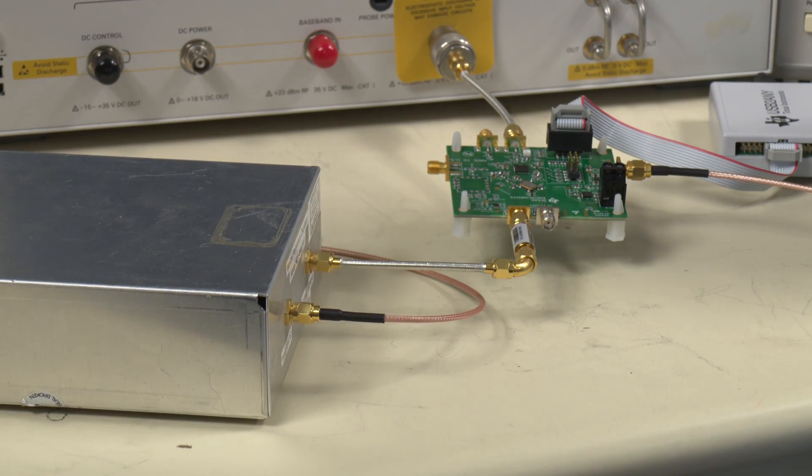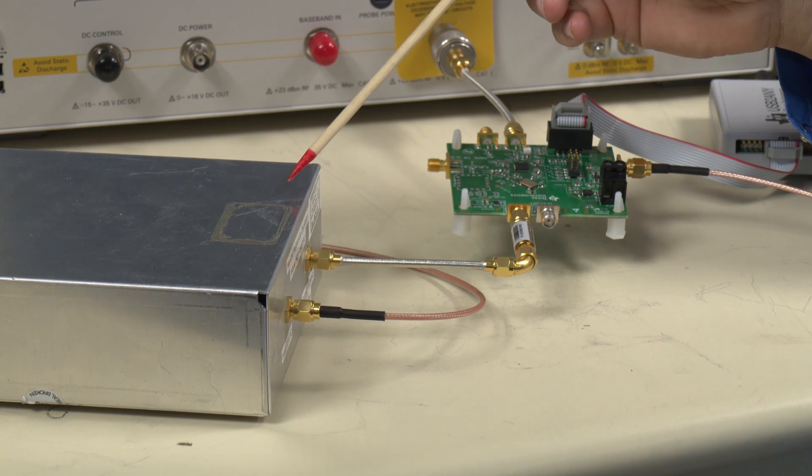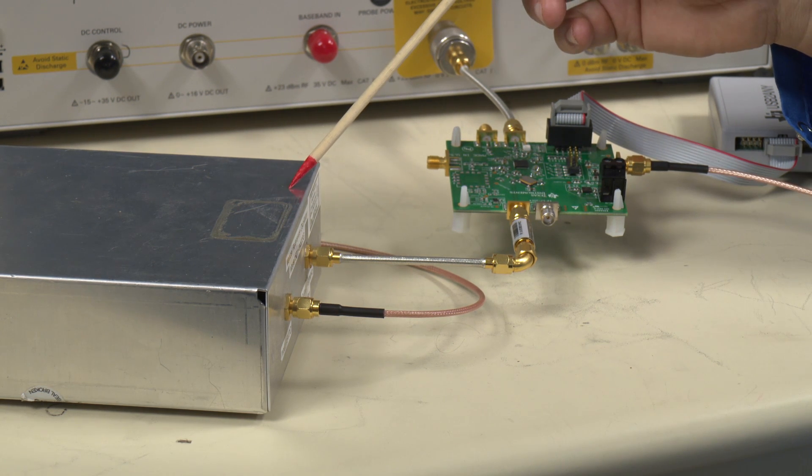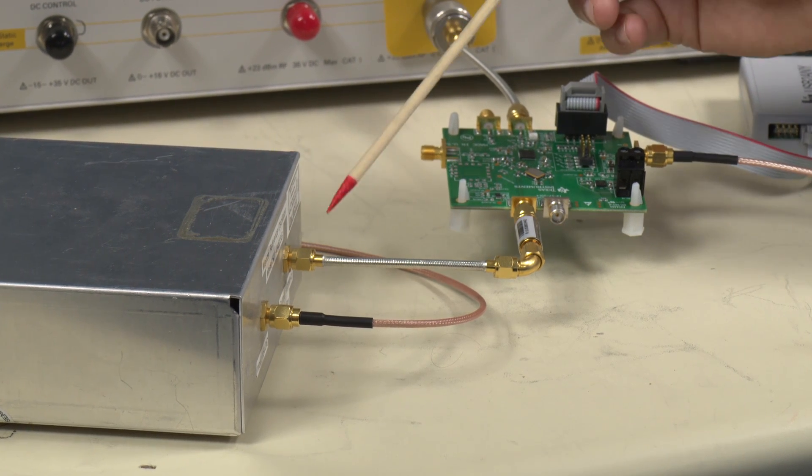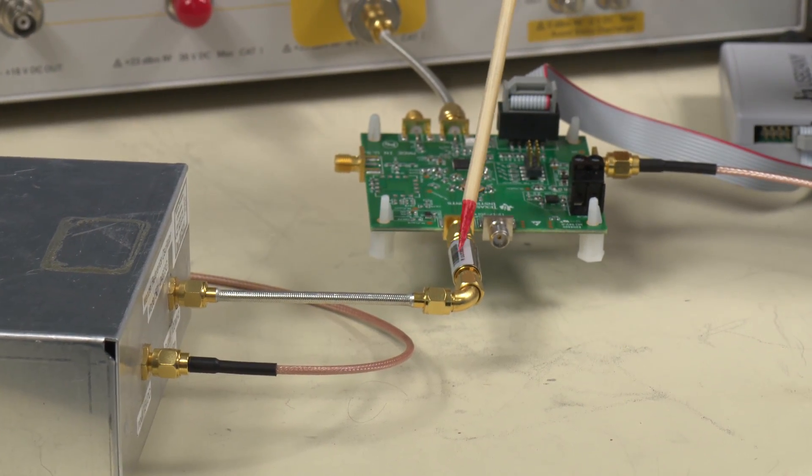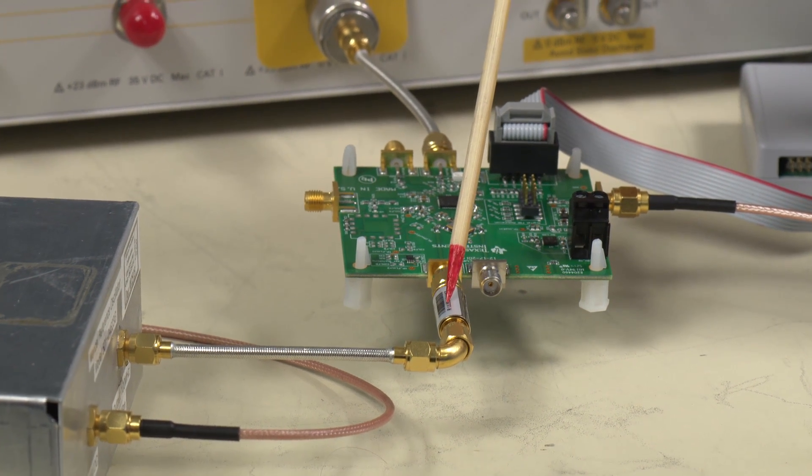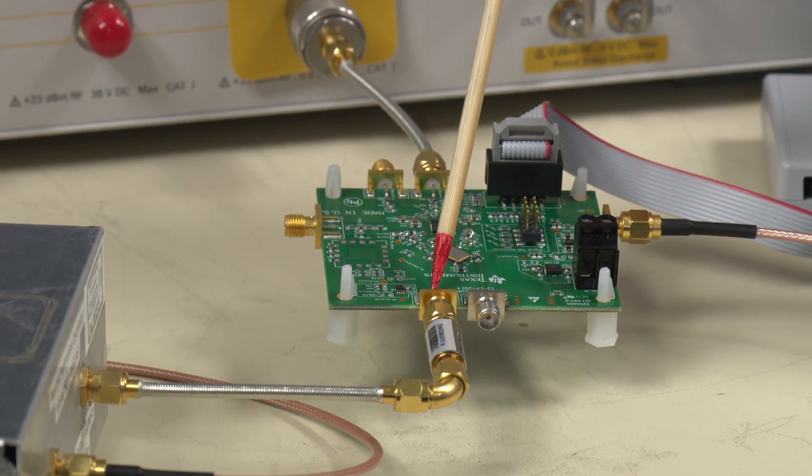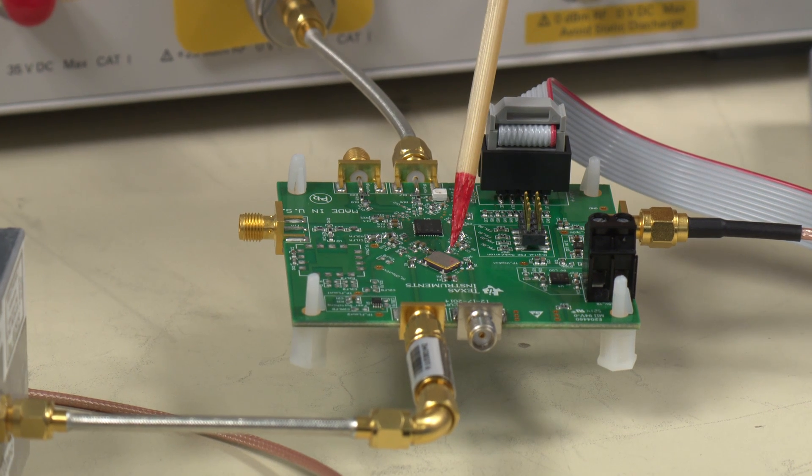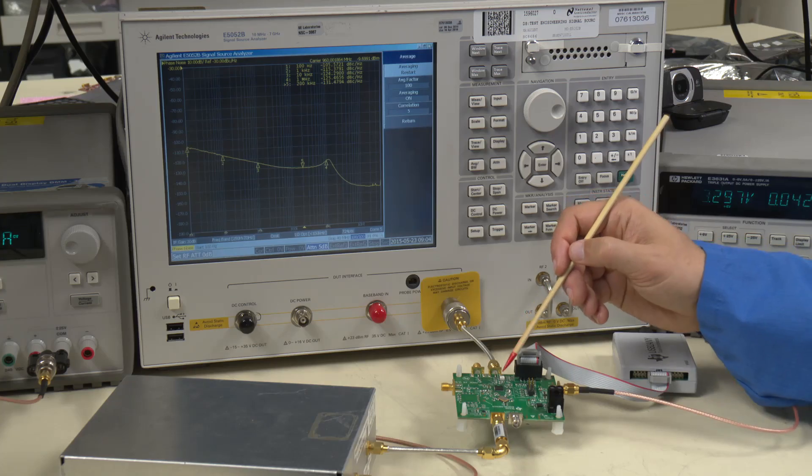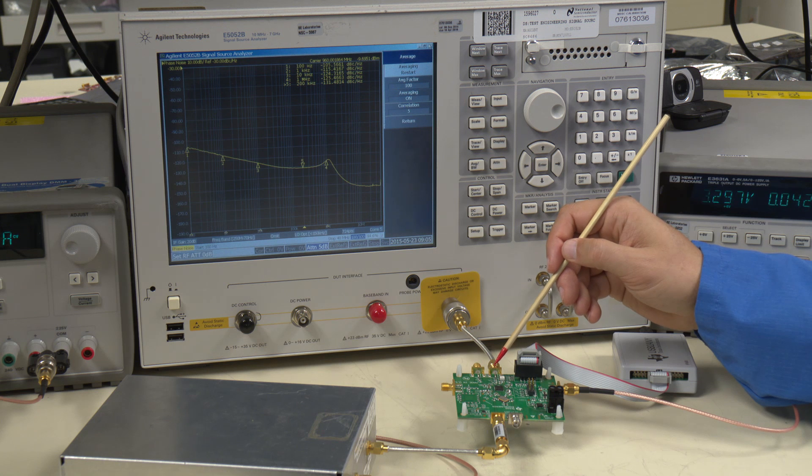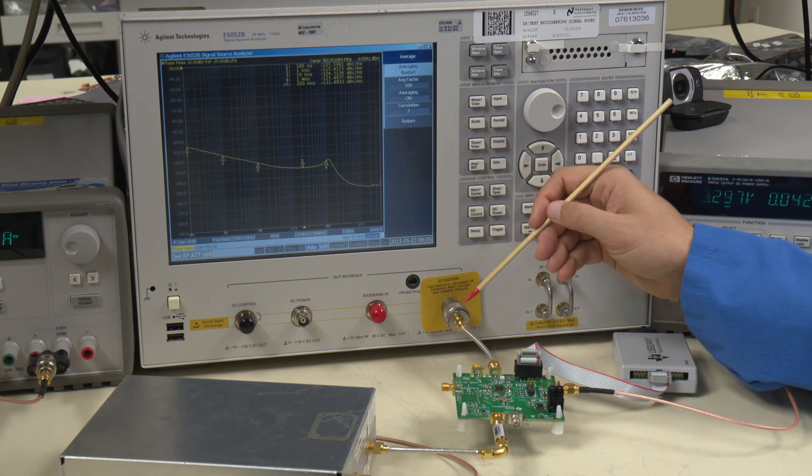To measure the PLL phase noise, we're going to start with a Wenzel 100 MHz crystal. This is very, very clean. It's high output power plus 14 dBm. And we can be sure that this particular instrument is not going to disrupt our PLL phase noise measurements. The output here at plus 14 dBm is going to go through this limiter, which is going to limit the amplitude of the signal but not degrade the slew rate. And then this is going to come in all the way to the LMX2571, which is here.